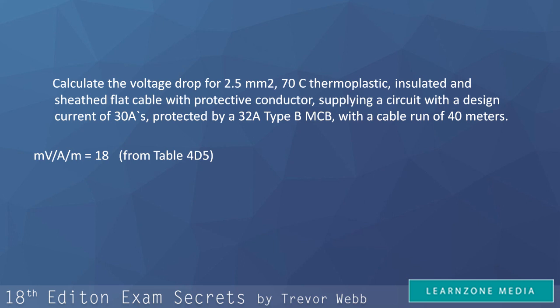Then we can see that the design current is 30 amps. This is our second value. Finally, we can see that the length of the run is 40 metres. And with this, we have everything we need to calculate the voltage drop required and to answer the question.